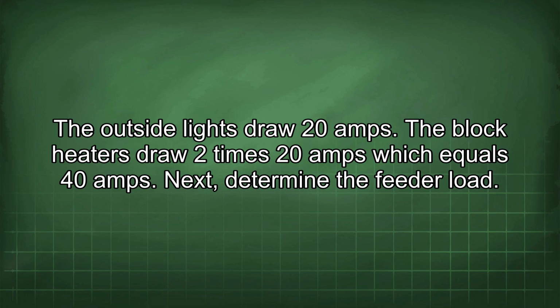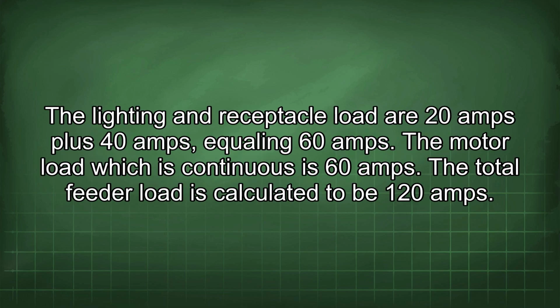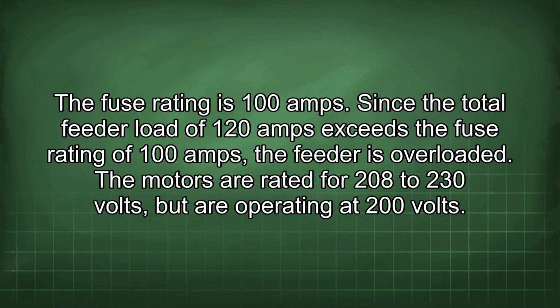Next, determine the feeder load. The lighting and receptacle load are 20 amps plus 40 amps, equaling 60 amps. The motor load, which is continuous, is 60 amps. The total feeder load is calculated to be 120 amps. The fuse rating is 100 amps. Since the total feeder load of 120 amps exceeds the fuse rating of 100 amps, the feeder is overloaded.